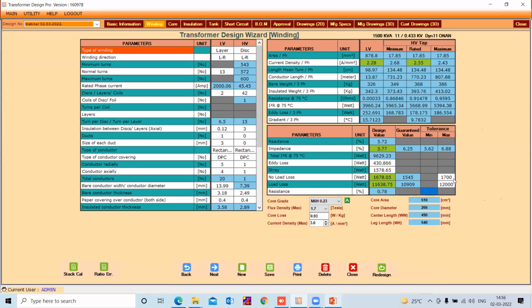It's okay. Load loss is also designed at 11,638.7 watt. The guaranteed value, as was on the basic page, was 12,000 because it was 10,909 the tolerance as per the IEC. Now here also you can see, friends, you are in a position to edit the maximum losses that is to be considered while designing. And the software is such an intelligent one, it will try to go towards the maximum load loss or the no load loss specified and design in that fashion. You can see the no load loss. When the maximum allowable value is 1700, it has designed at 1678. Whereas load loss, when it has been maximum specified as 12,000, it has designed at 11,638.